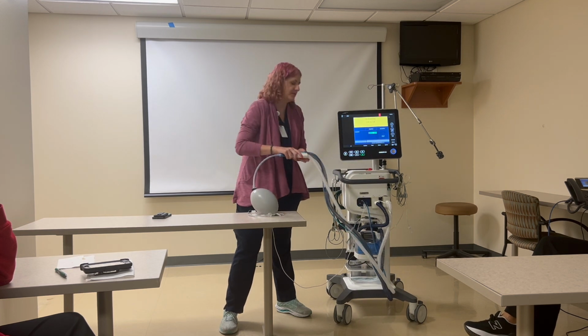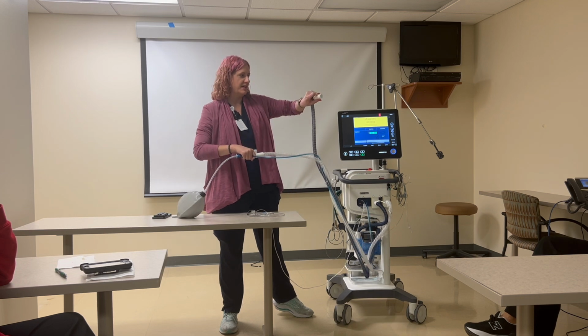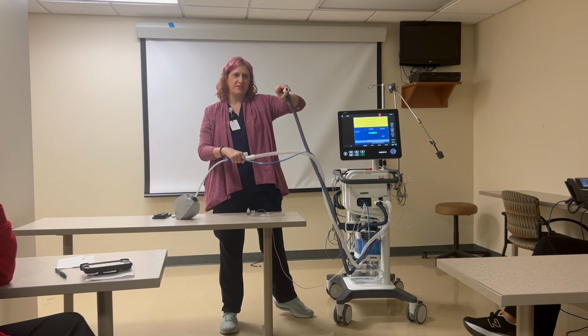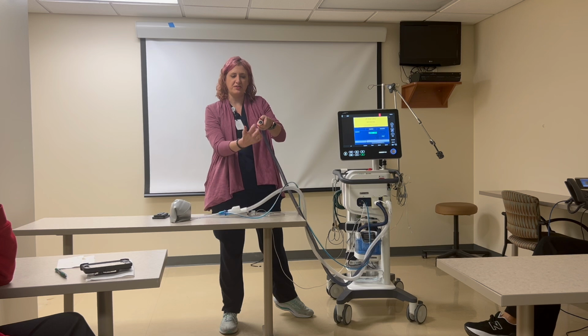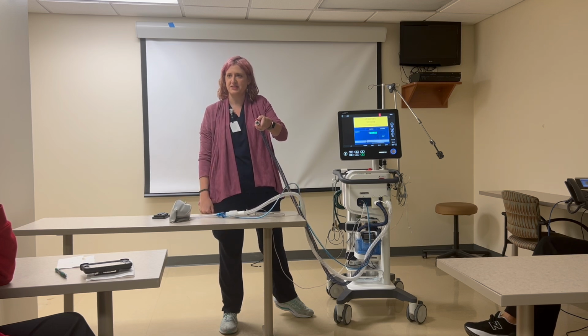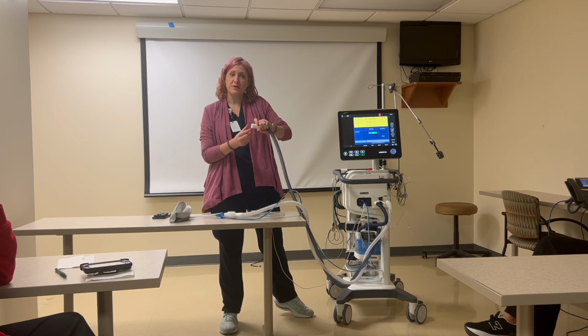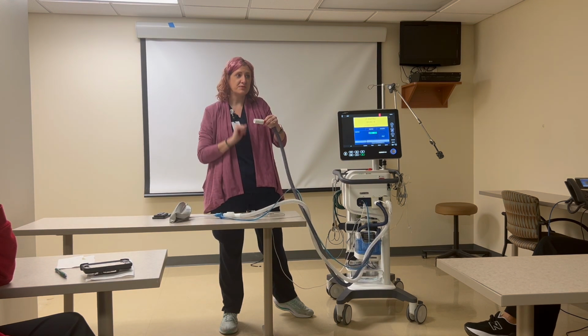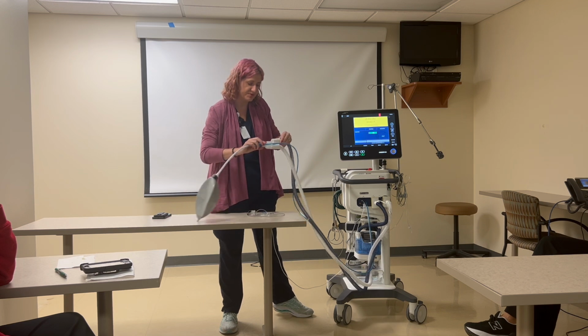That little temp probe that sits in there just hangs down. So if we ever have that circle facing down, then all of that water and condensation is sitting on that temp probe, and then we can't effectively humidify the air for them. So that's why we want that circle to be facing up, so we don't cause any condensation or any troubles to our heaters.